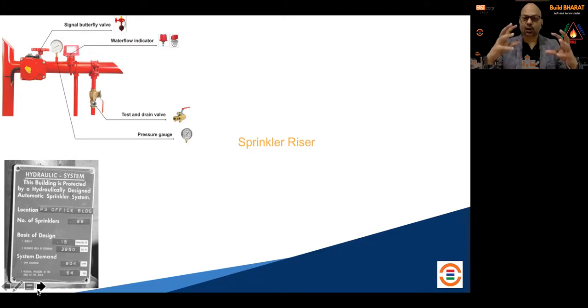Your zone control valve assembly in the riser should have all the right ingredients - flow switch, pressure gauge, zone control valve, drain, test and drain valve - everything has to be in order, and it is given very clearly in the code standard.